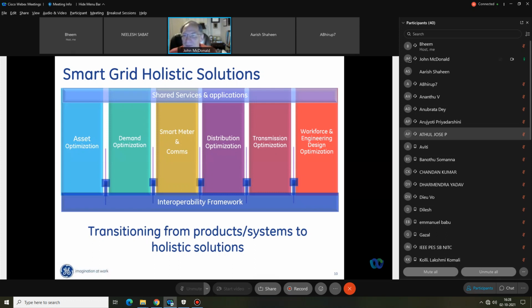This is actually the strongest business case today because of the previous lack of investment in distribution. Secondly, typically the power factor on the distribution part of the grid is not very good. There's a lot of room for improvement, and that's why the benefit cost ratio is so strong, around 5 or 6 to 1. For every dollar we invest in distribution optimization, we get $5 to $6 back. So there's a lot of focus today on distribution, which I'm going to talk about here.